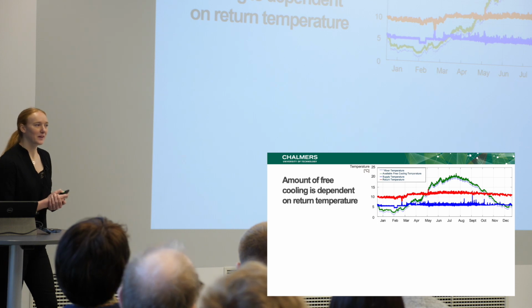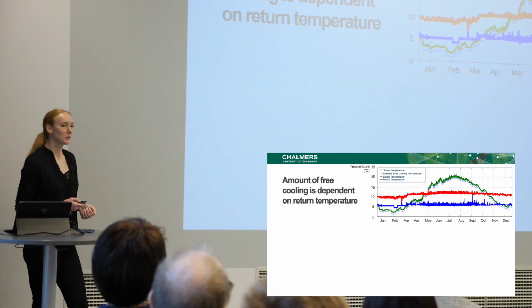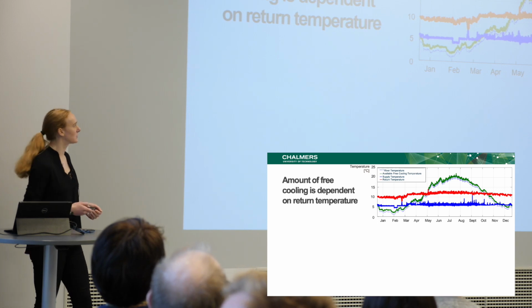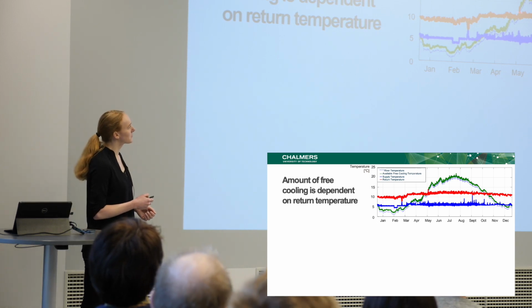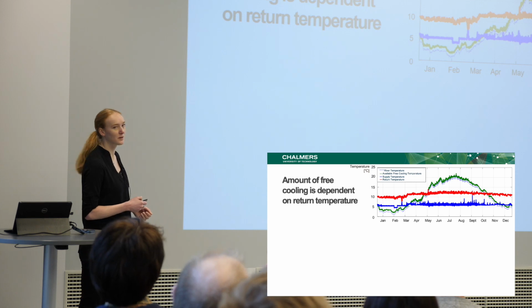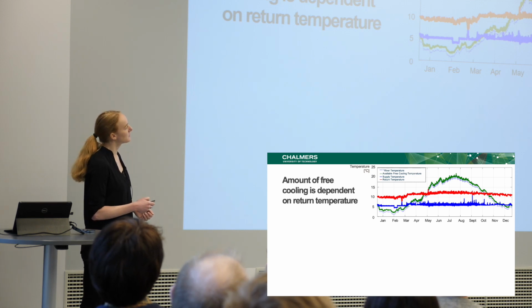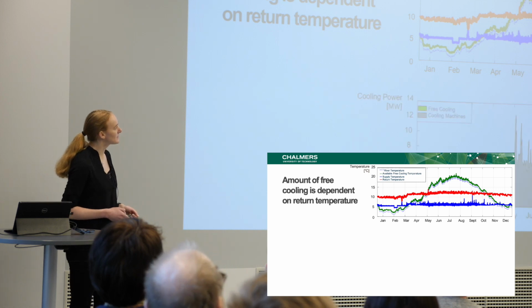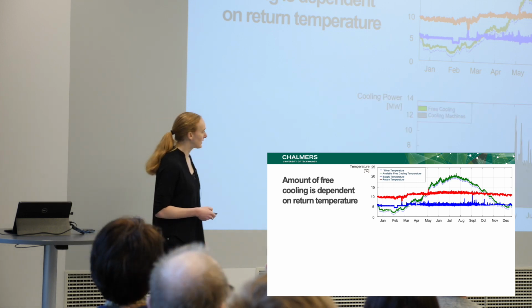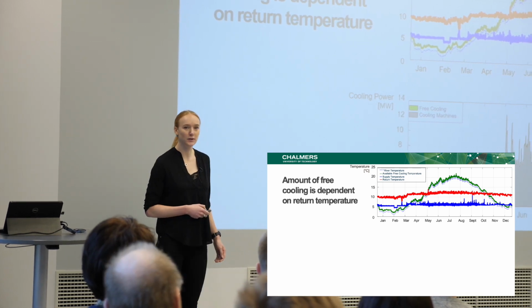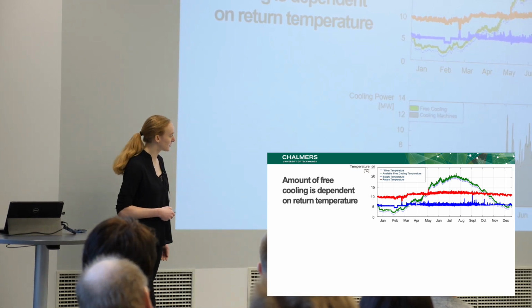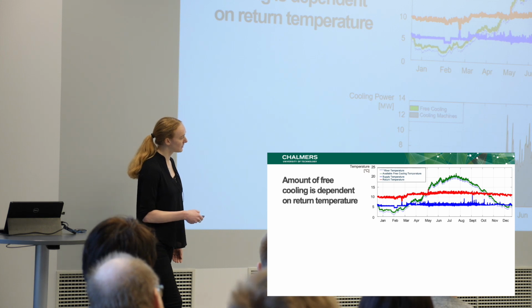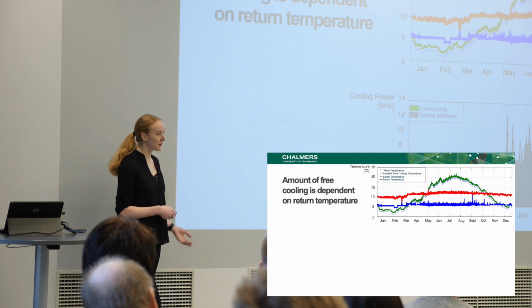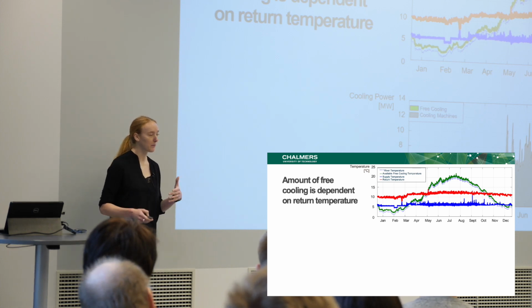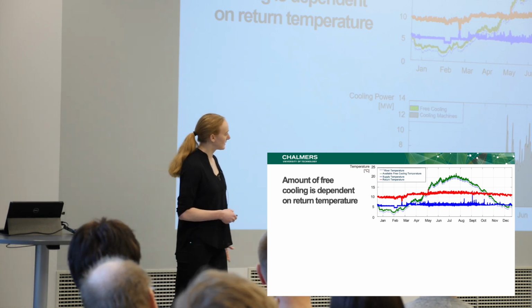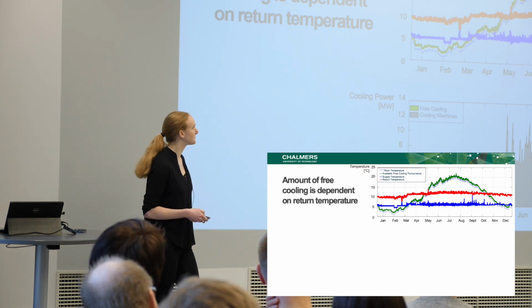And now a little bit on how much free cooling can be used in connection to the temperatures. This one you recognize from before. This is the supply and return temperatures from 2017, and also the river temperature for that year. With these temperatures, the free cooling share for the production of 2017 was actually 28%, corresponding to these green areas. So that's free cooling in either 100% free cooling or in the combi operation. And the rest in the gray is produced with cooling machines.